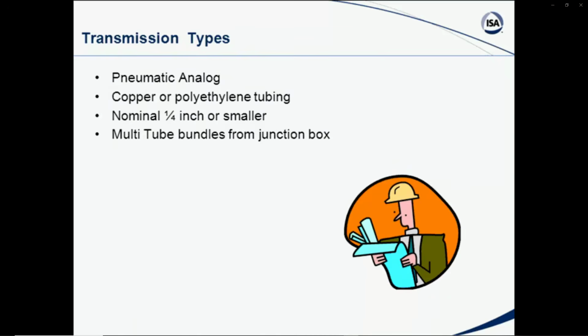So on the pneumatic type, you say, well, we don't do much pneumatic work anymore. Well, that may be true, and it's not in some cases, and the test is probably set up where it covers a little bit of everything, and we need to be aware that pneumatics do exist. We use copper or polyethylene tubing, and many times you're using pneumatic actuated control valves, so you do have pneumatic signals. You do have copper or stainless steel or polyethylene tubing. You do have some characteristics you have to watch, and you're using normally 1/4 inch and smaller.